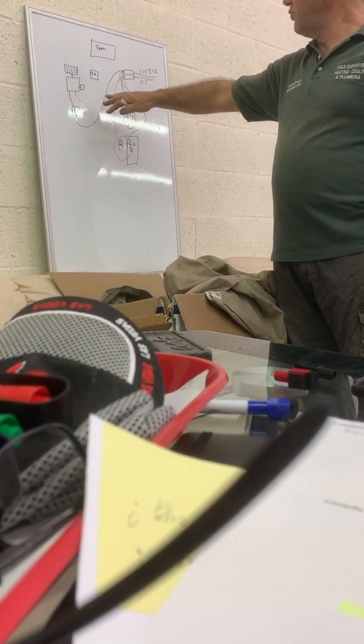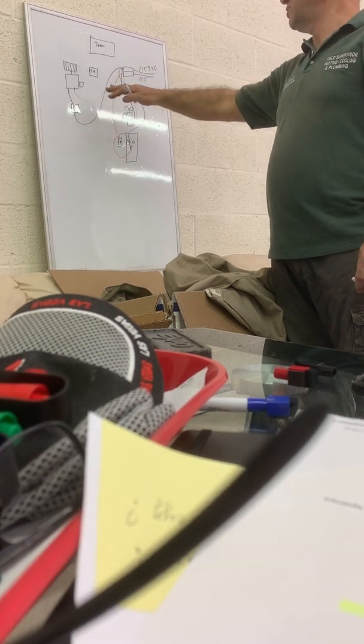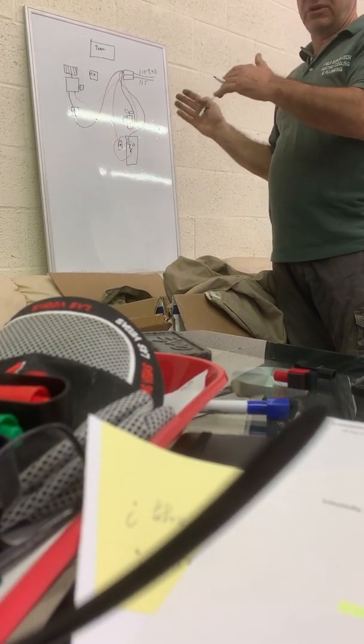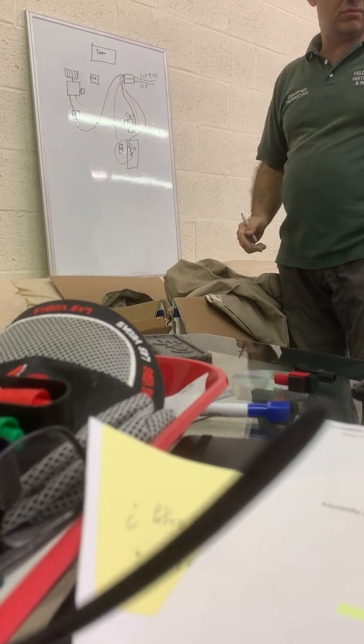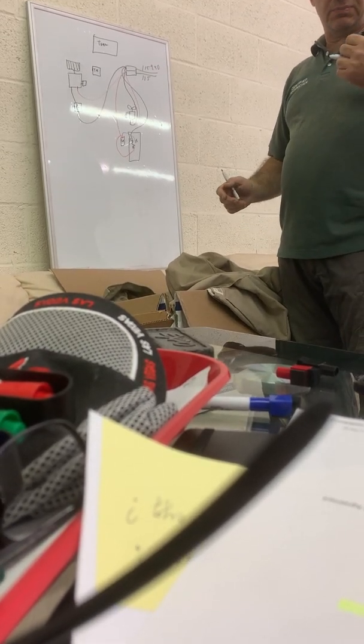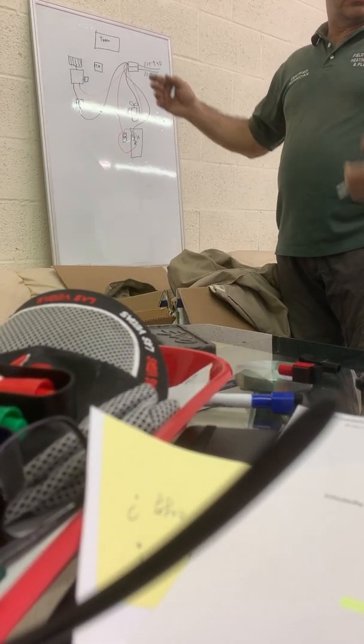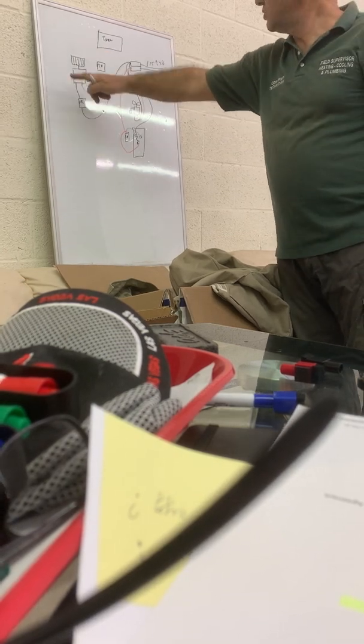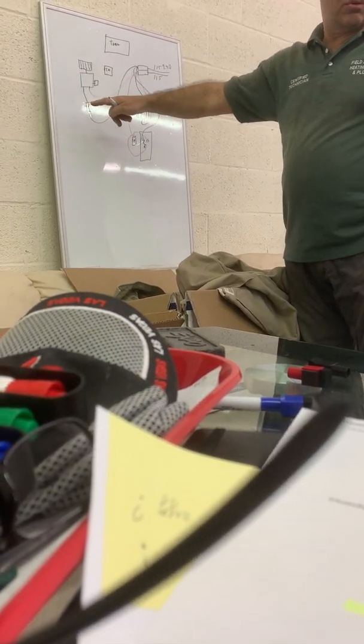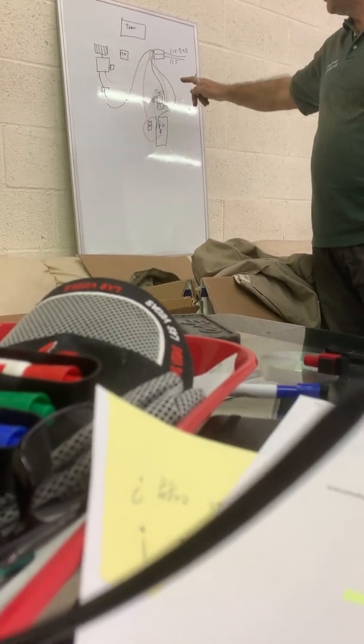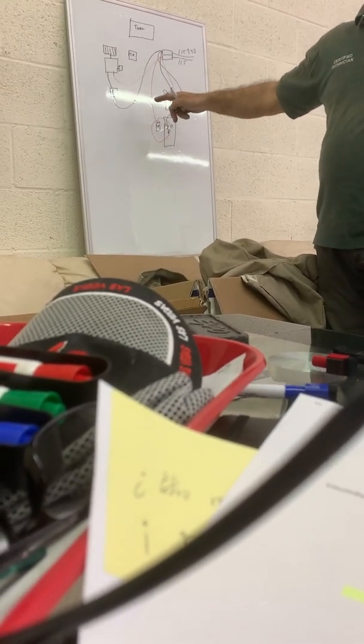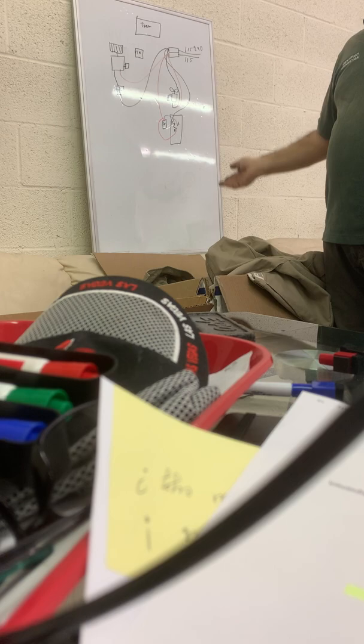You see, we throw 240 volts throughout the unit. So right now we're talking about a package unit. Because if it's a split system, then it's going to be 115 on the blower side and 240 on the condenser side. Okay, but if it's packaged, it's all 240.